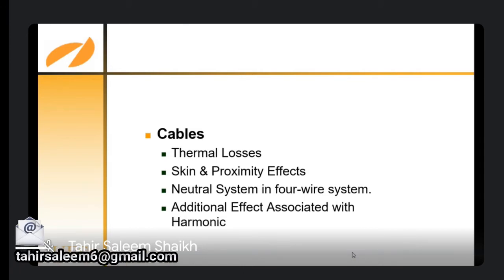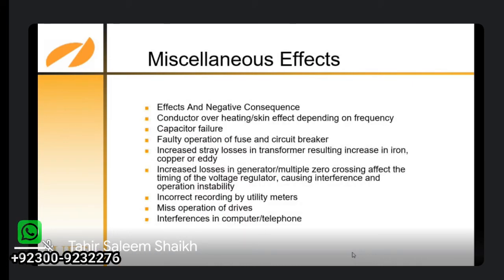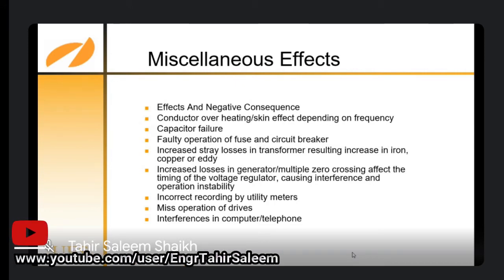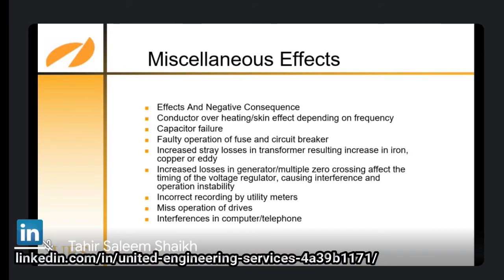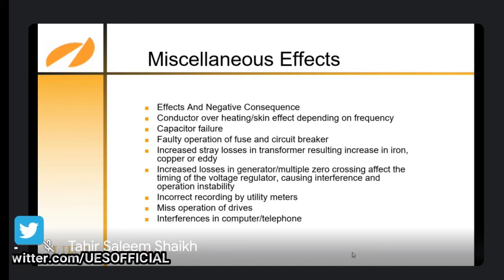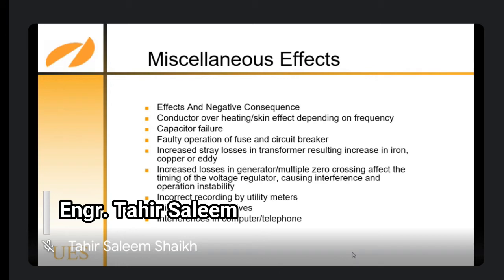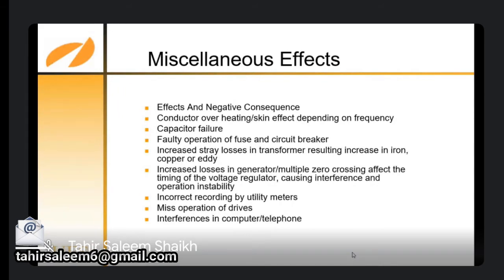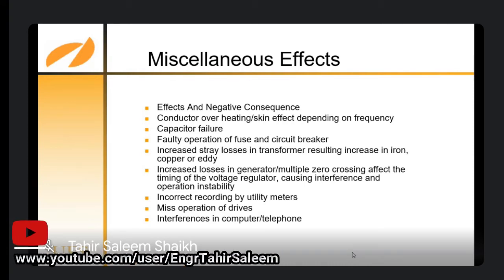Thermal losses increase in cables through skin and proximity effects, neutral in a 4-wire system, and additional effects associated with harmonics. You can see in this example the miscellaneous effects and negative consequences: conductor overheating, skin effect depending on frequency, capacitor failure, faulty operation of fuses and circuit breakers, increased stray losses in transformers resulting in increased iron and copper losses, increased losses in generators, and multiple zero crossings affecting the timing of the voltage regulator, causing interference and operation instability. Incorrect recording by utility meters, misoperation of drives, because your utility meters take readings on average. Harmonics disturb these average readings. Misoperation of drives, interference in computers or telephones.